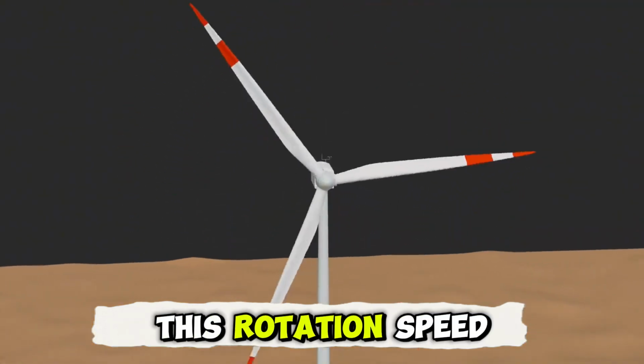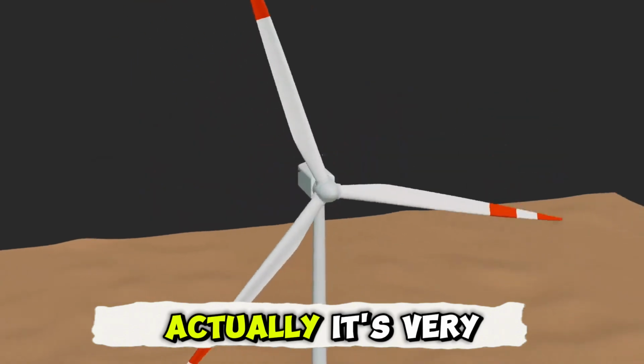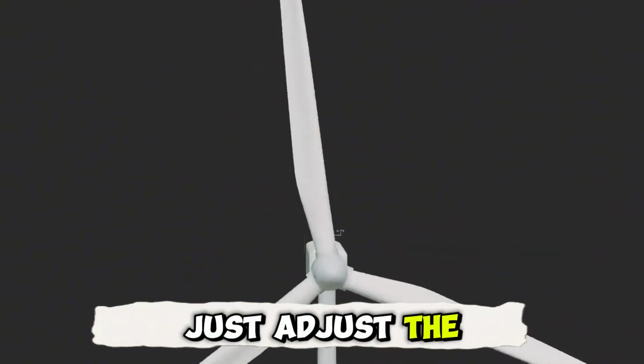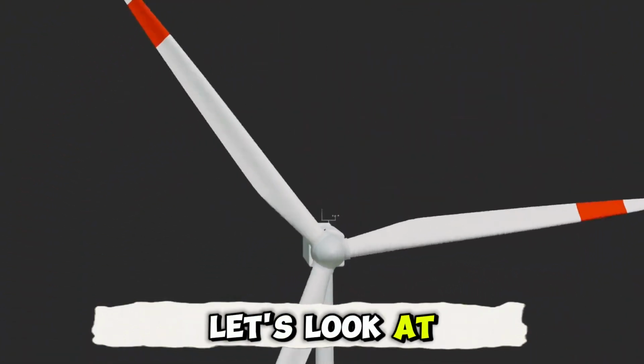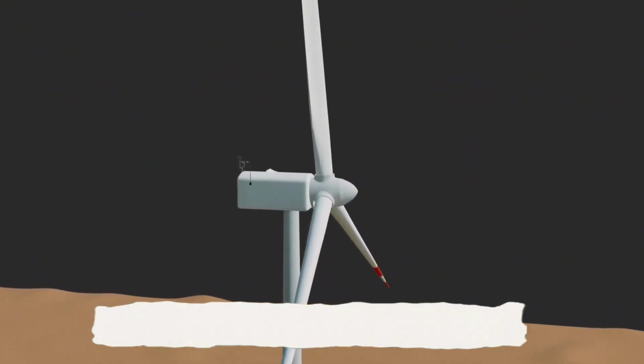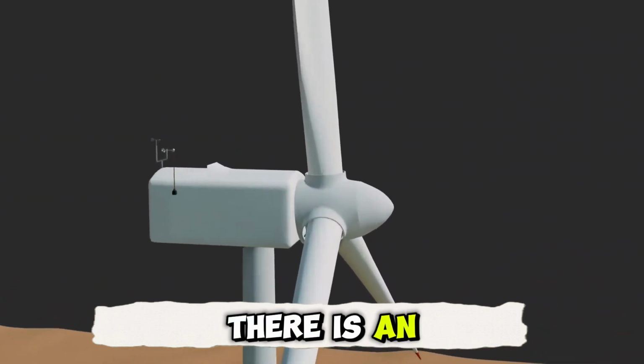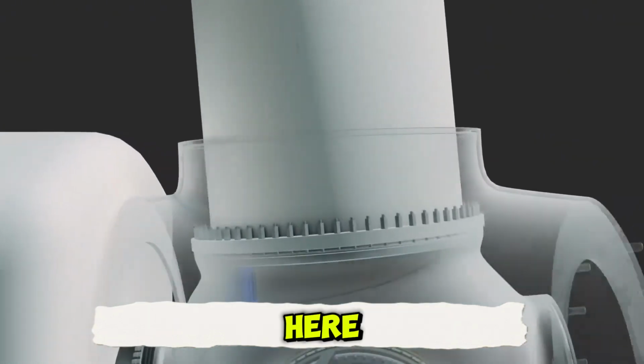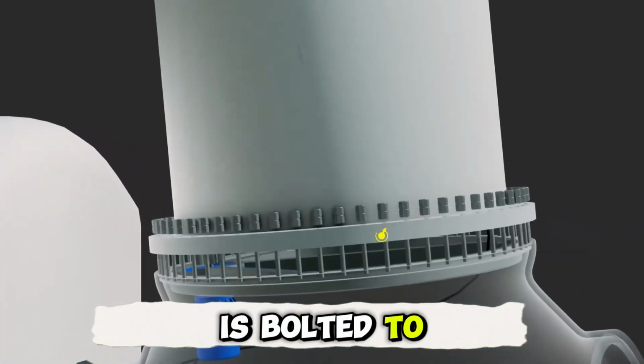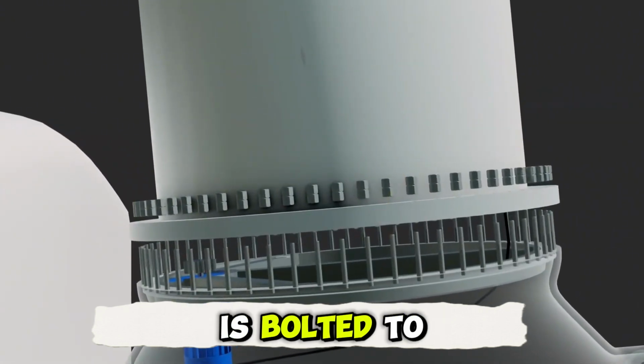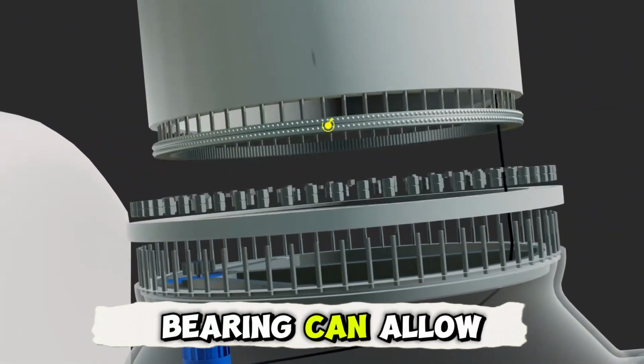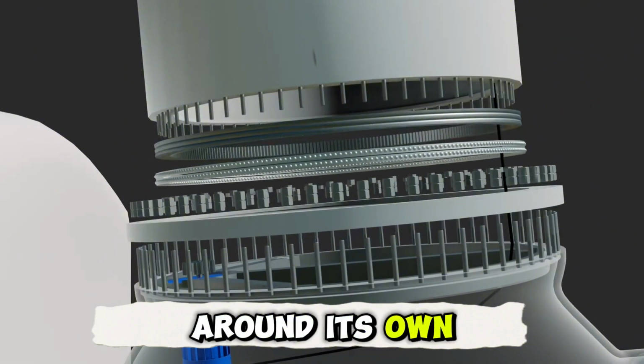Then how is this rotation speed controlled? Actually, it's very simple. Just adjust the angle of the blades. Let's look at the connection point of the blade. There is an integrated bearing mechanism here. The outer ring of the bearing is bolted to the hub, the inner ring is bolted to the blade. This kind of bearing can allow the blade to rotate around its own axis.